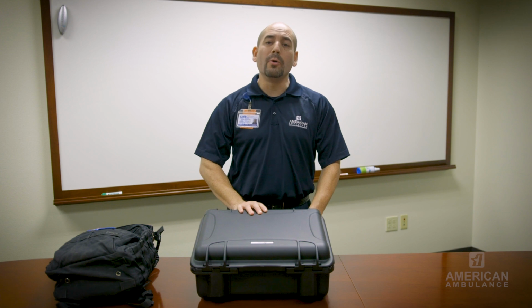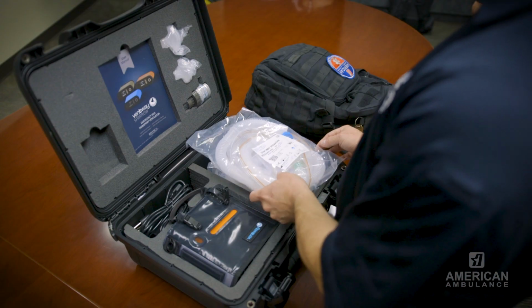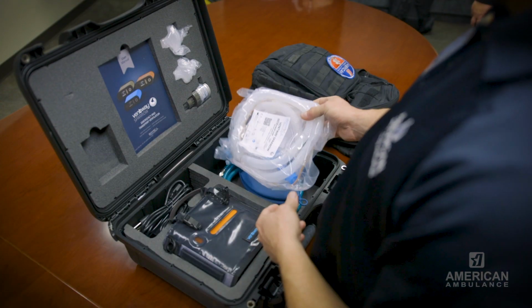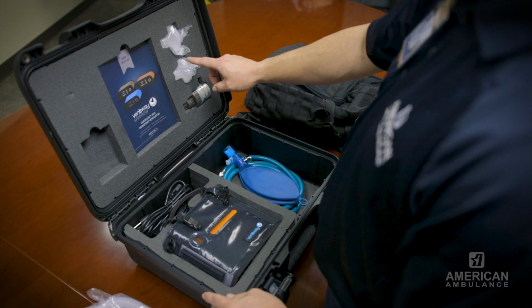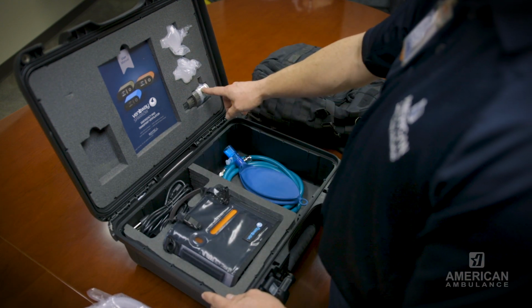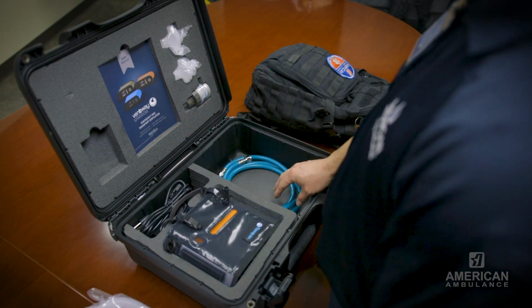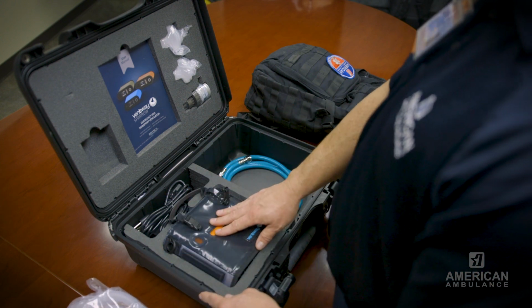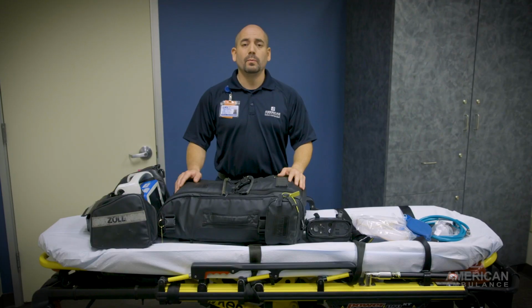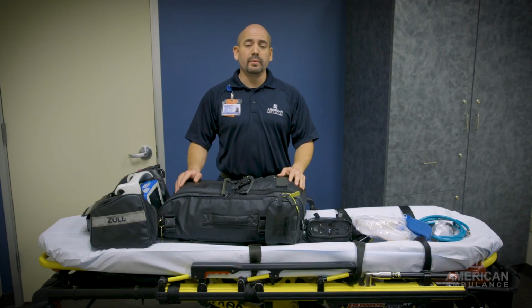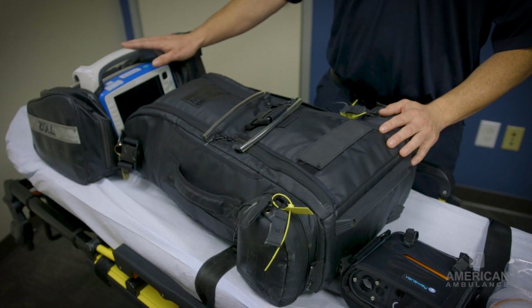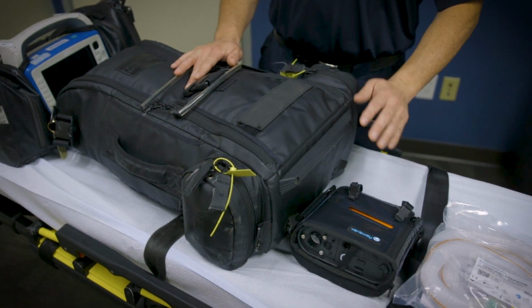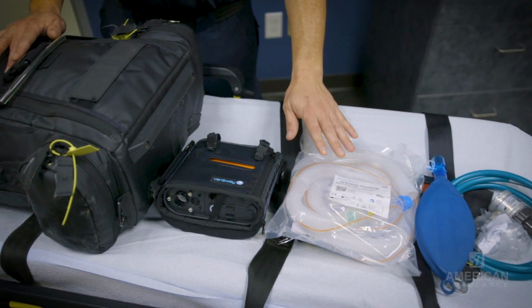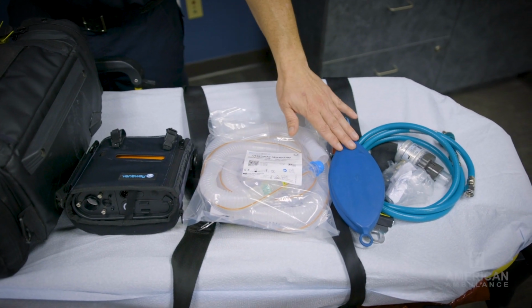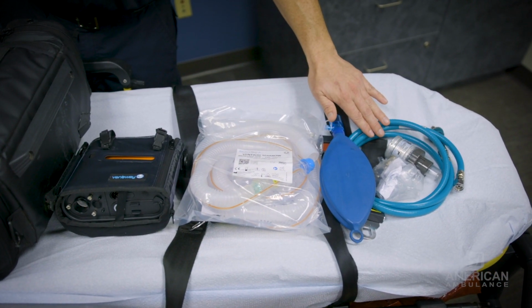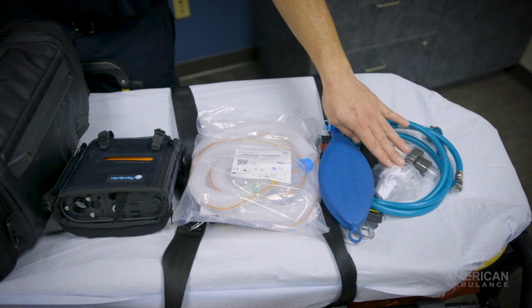Once you pick up the ventilator, open the box and ensure that you have 1 adult circuit, 1 pediatric circuit, 2 HME bacterial filters, the oxygen blender, the test lung, the high pressure oxygen tubing, the Ventway Sparrow, and the charging cord. When you arrive on scene, take the following pieces of equipment with you to the patient's bedside: the Zoll monitor, the oxygen bag, the Ventway Sparrow, the proper circuit, the test lung, the high pressure O2 line, the oxygen blender, and the filter.